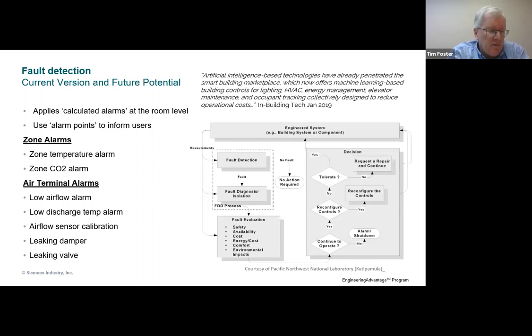So from that standpoint, you could see some pretty significant operational savings, because now rather than doing maintenance based on a time routine or a rule of thumb, like changing the filter every 6 months, now you can do it based on actual demand and prioritize those issues in terms of impact on the organization.